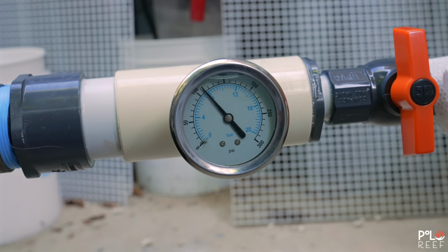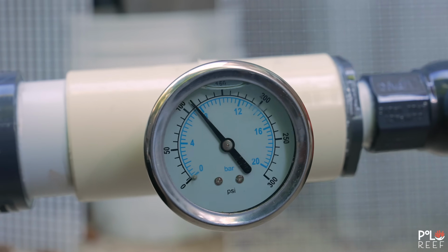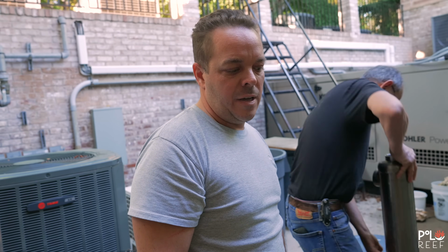They head back to check on the heat exchanger to see if the pressurization is holding. As you can see by the gauge, before and after, it's still held at 110 psi, so there's no leaks in the heat exchanger. As far as the pump downstairs, everything looks clean. The shaft seal has a little damage to it, so we're going to replace it, but it's not the source of our copper either. There is no leak in it, so we're going to reinstall it and keep on our quest.